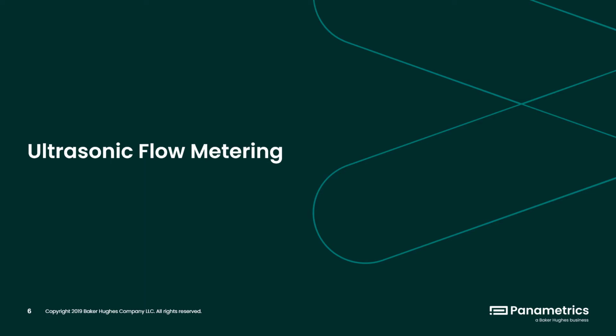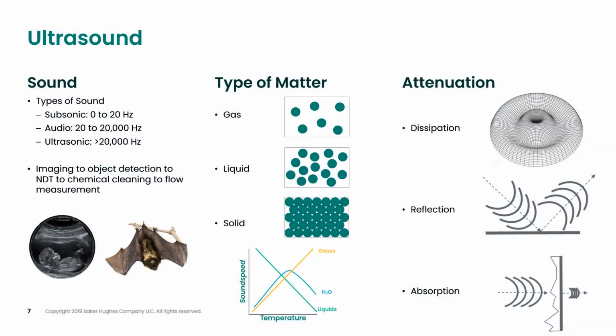Before going too far into the advantages and value that ultrasonic flow metering brings to your process unit, we should quickly review the basics of ultrasonic flow measurement. Sound waves are vibration energy that travel through gas, liquid, or solids. Sounds can be classified as either subsonic, audio, or ultrasonic. Ultrasonic are sound waves above 20,000 Hz. Ultrasound is used every day in nature and in industry. Ultrasound is used for object detection with bats and dolphins, to imaging at hospitals, to non-destructive examination of materials, for chemical cleaning, and then finally to flow measurement.